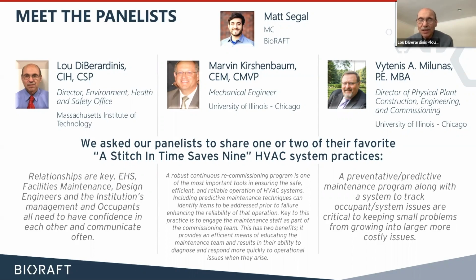And so whereas in our typical approach, we would look at designing a local exhaust ventilation system, fume hoods, biological safety cabinets, other kinds of local exhaust ventilation. In this case, we can't do that, can't control at the source. So we do have to think about dilution as the control for reducing exposure. And that has forced us to know a lot more about general HVAC systems rather than local exhaust control systems.